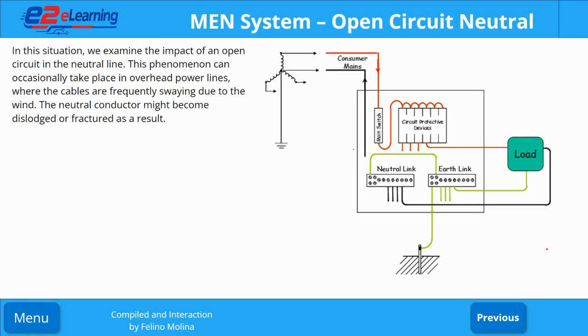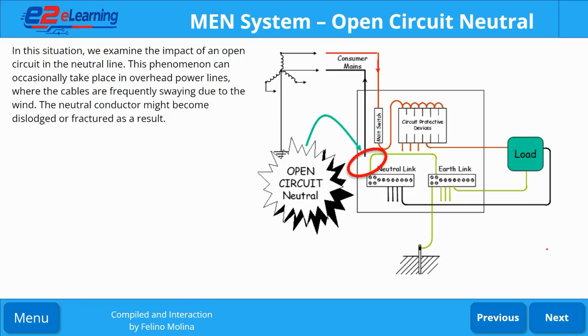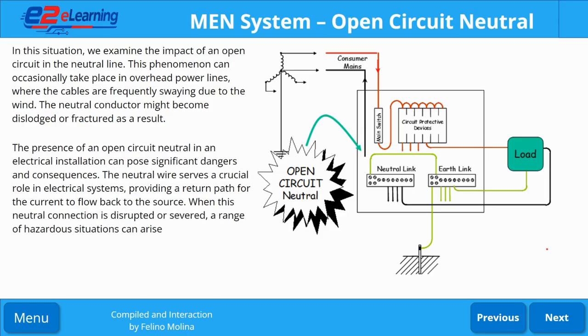In this situation, we examine the impact of an open circuit in the neutral line. This phenomenon can occasionally take place in overhead power lines, where the cables are frequently swaying due to the wind. The neutral conductor might become dislodged or fractured as a result. The presence of an open circuit neutral in an electrical installation can pose significant dangers and consequences.